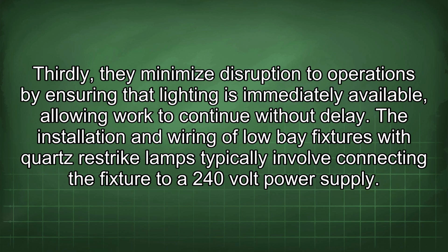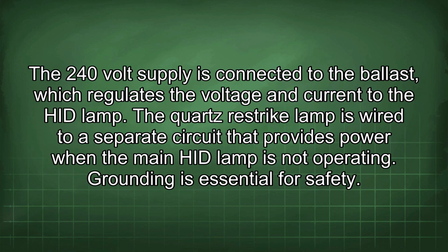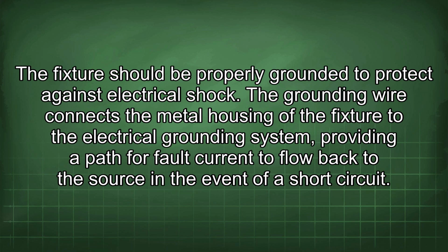The installation and wiring of low-bay fixtures with quartz restrike lamps typically involve connecting the fixture to a 240-volt power supply. The 240-volt supply is connected to the ballast, which regulates the voltage and current to the HID lamp. The quartz restrike lamp is wired to a separate circuit that provides power when the main HID lamp is not operating. Grounding is essential for safety. The fixture should be properly grounded to protect against electrical shock.